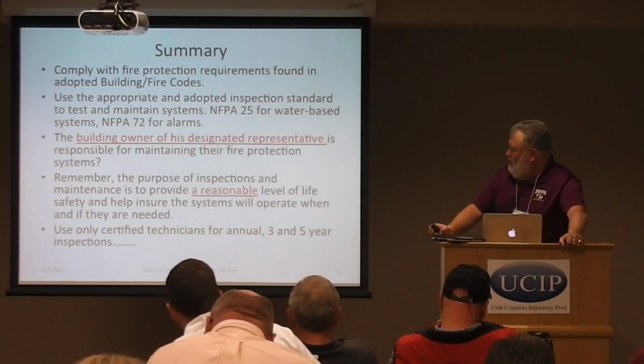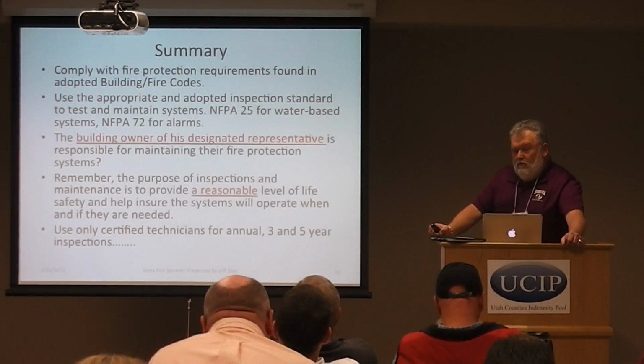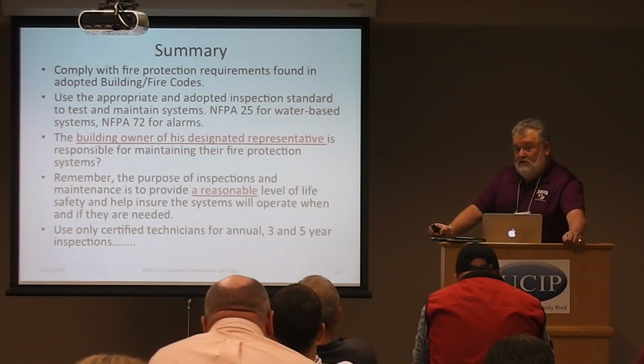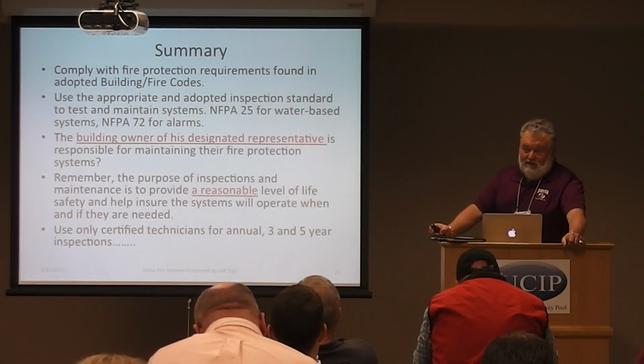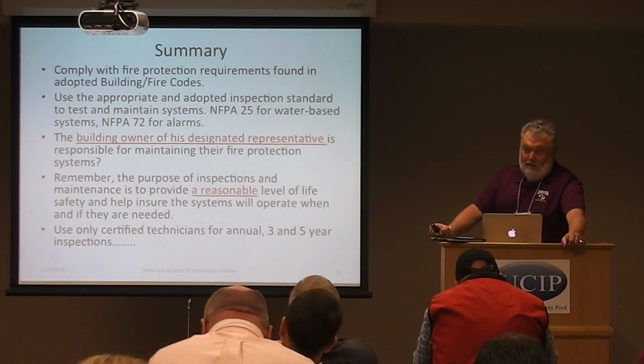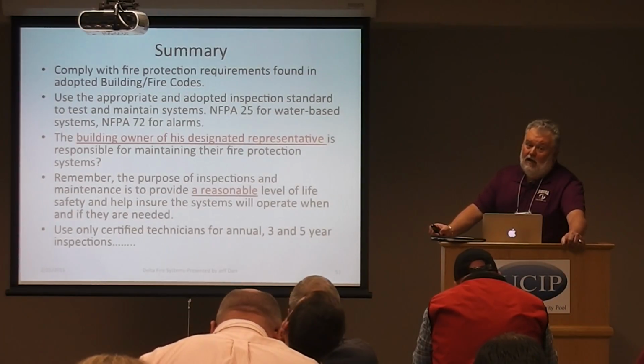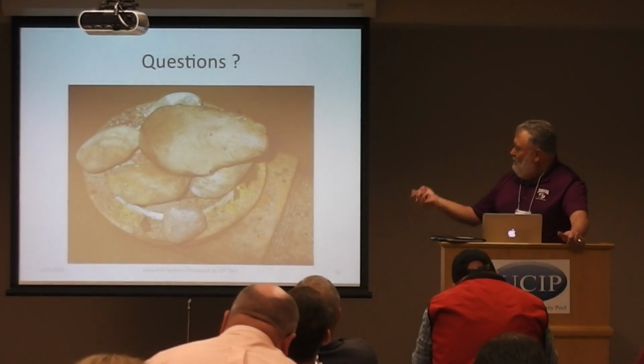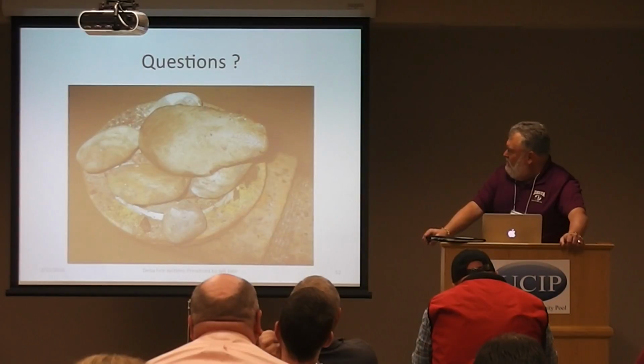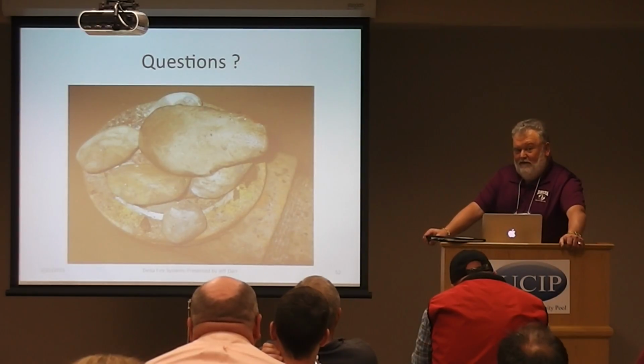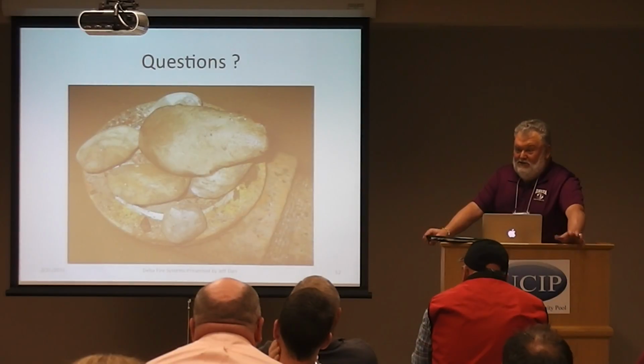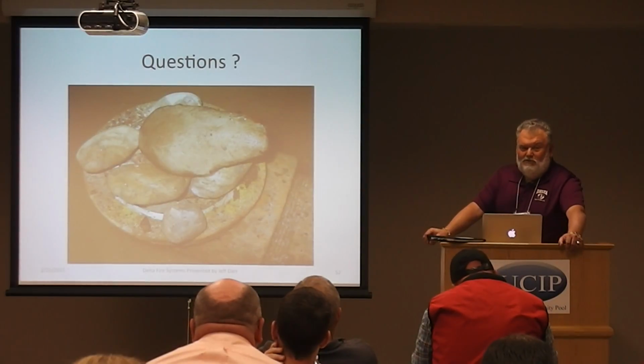And then on the annual, 3 and 5 years, make sure you use inspectors certified by the state at the appropriate level of certification for the system you have. Because if you've got a level 1 doing a deluge system around a transformer, he's not qualified for that. You're liable at that point. So that being said, here's the last slide I get a kick out of. We took all of those rocks out of that supply line right there. So I just stress, you have to make sure this system is going to work. I know you don't want it, but by gad, it better work when it's called upon.